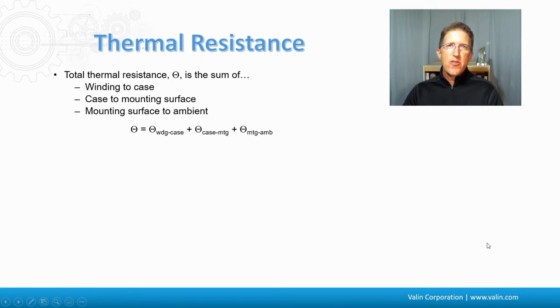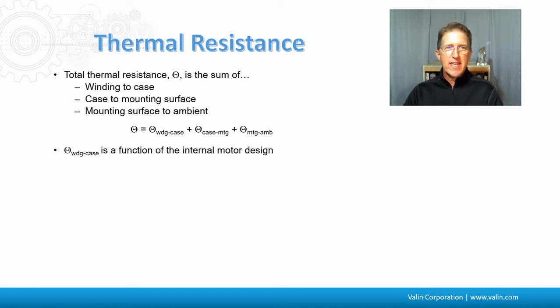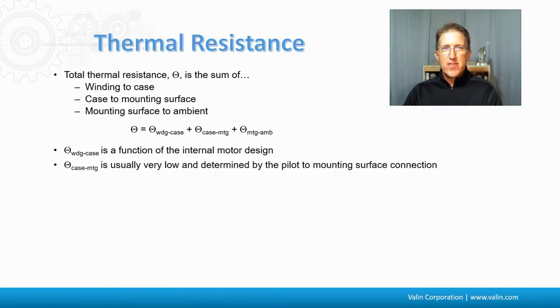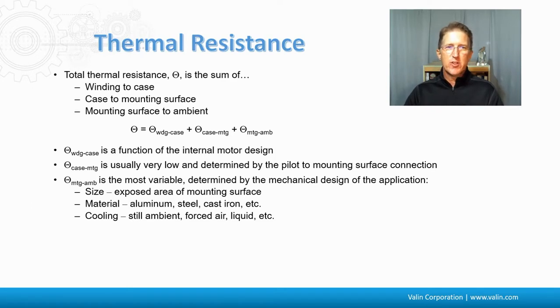There's also thermal resistance. The total thermal resistance theta is the sum of winding-to-case, case-to-mounting-surface, and mounting-surface-to-ambient thermal resistances. The winding-to-case is a function of the internal motor design. The case-to-mounting theta is usually very low, determined by how the motor is mounted to the surface. The mounting-to-ambient is the most variable, determined by the mechanical design of the application — whether the motor is in a box with no air cooling, and what materials and cooling are present.